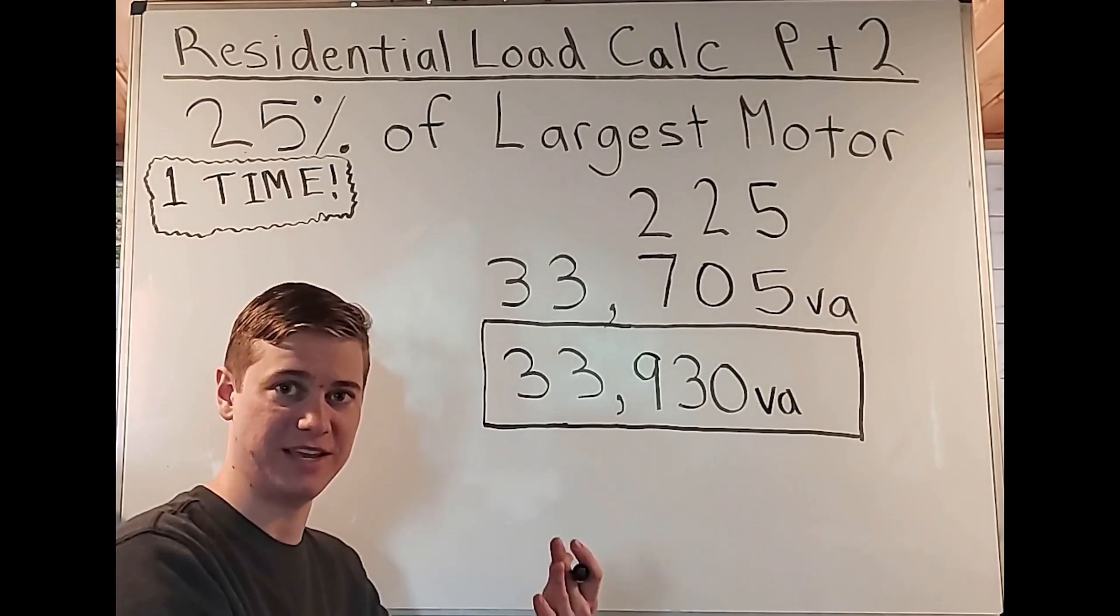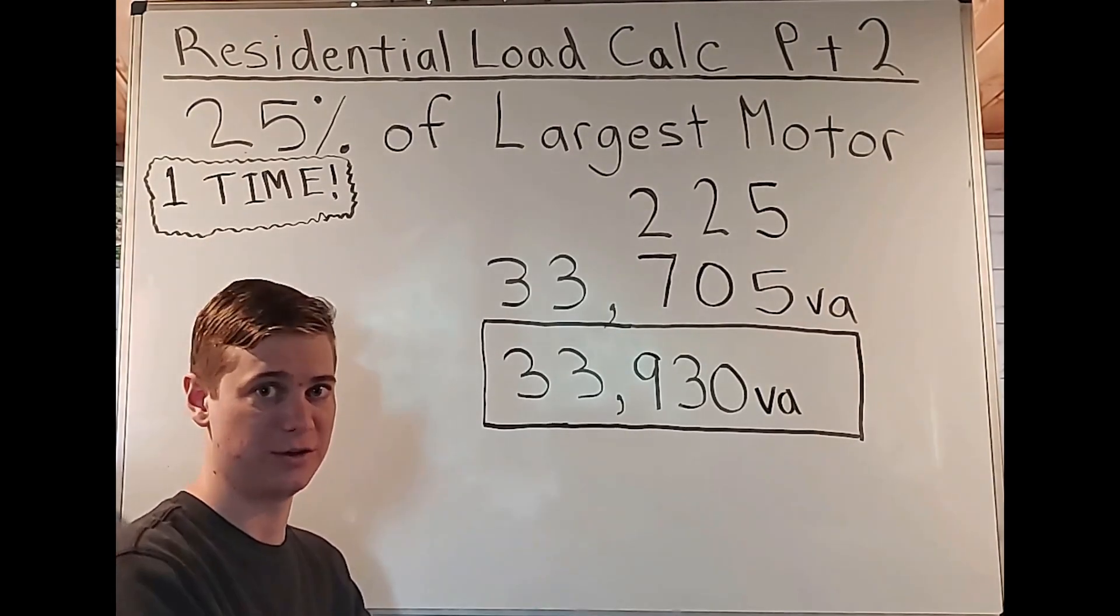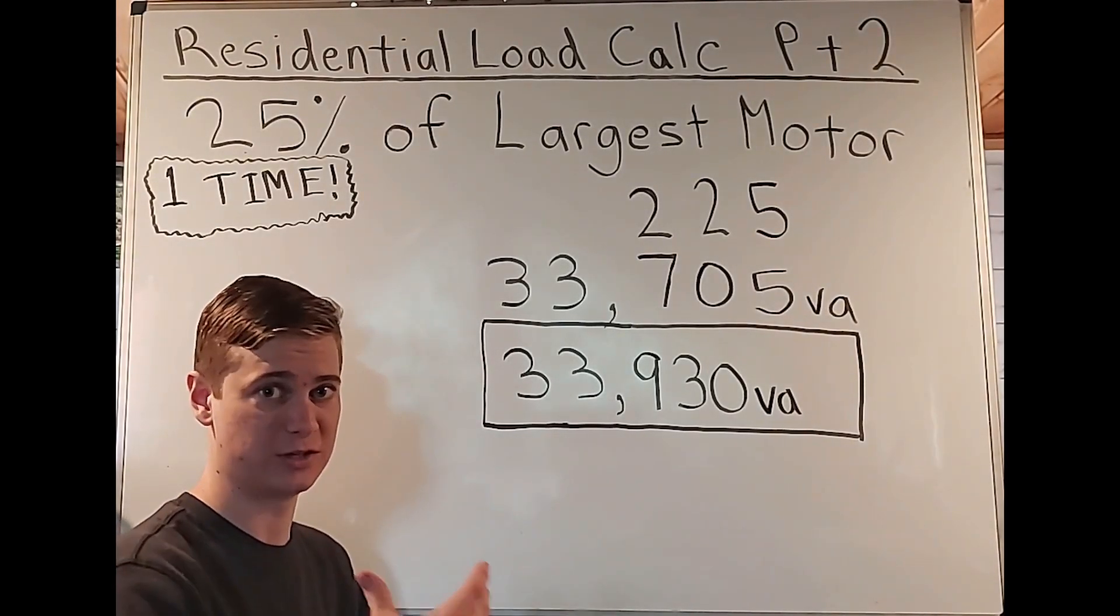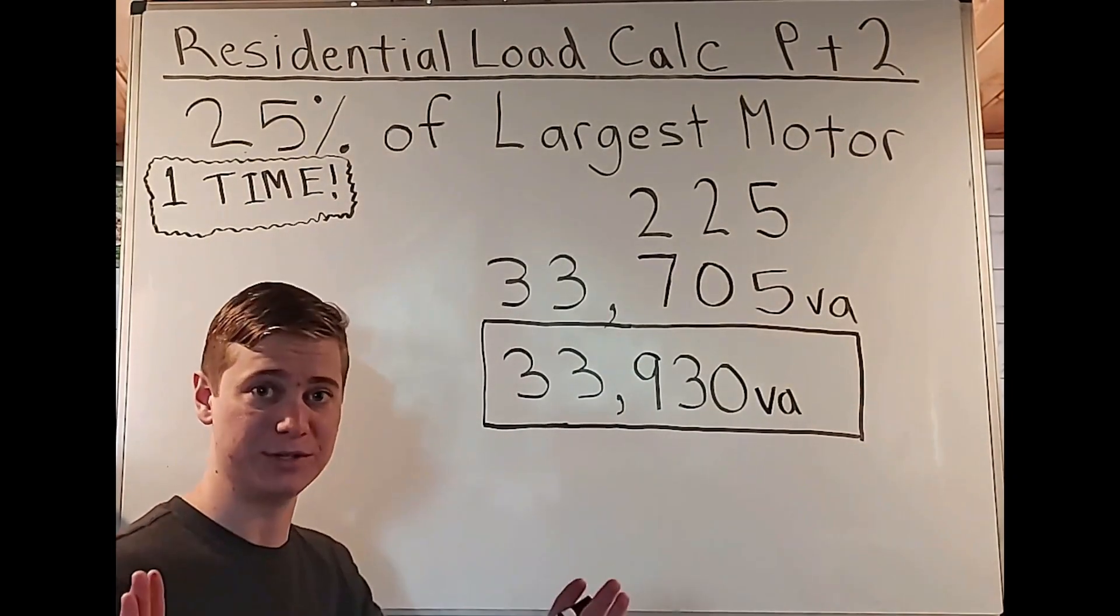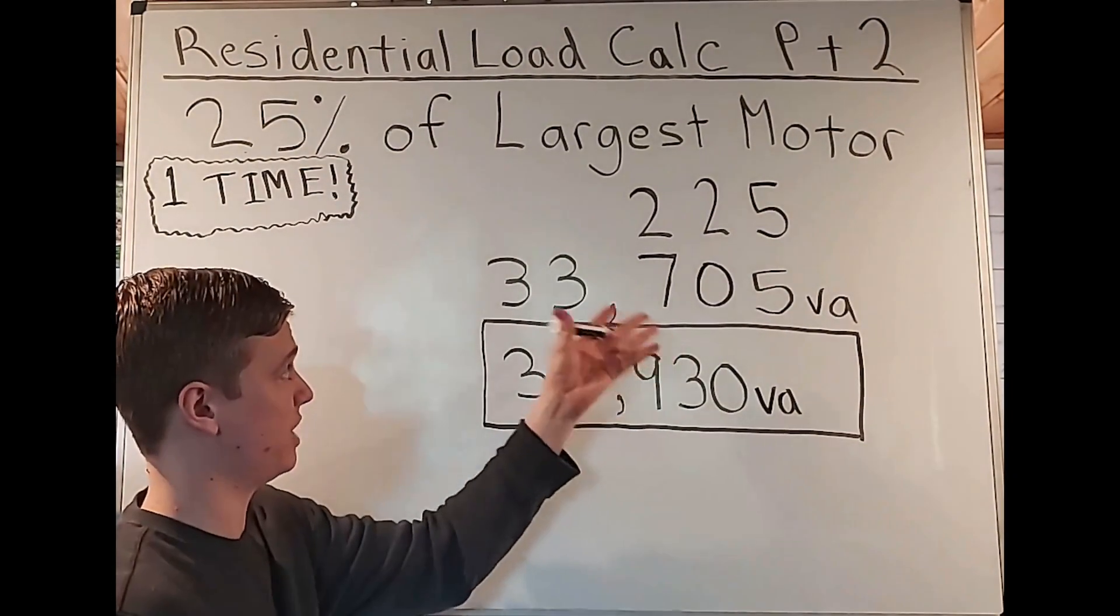And you'll see that basically, like I'm saying, it's the same thing always, you're going to just take the largest motor 25% of that, add that one time, no matter how many units you have to that final number that you got.